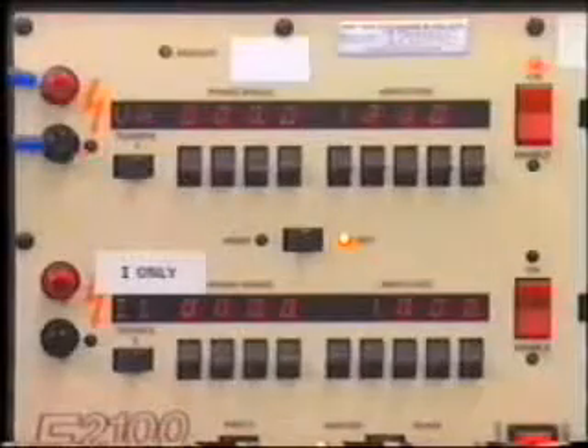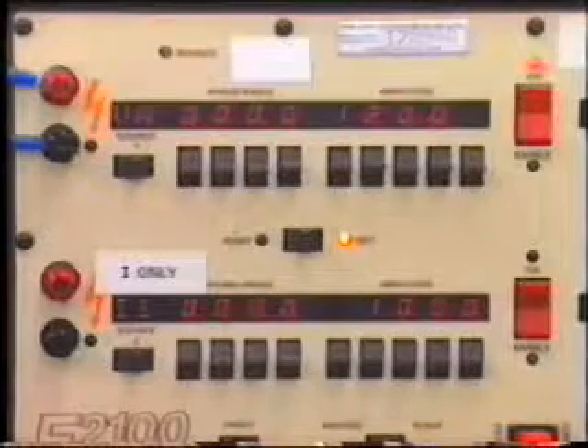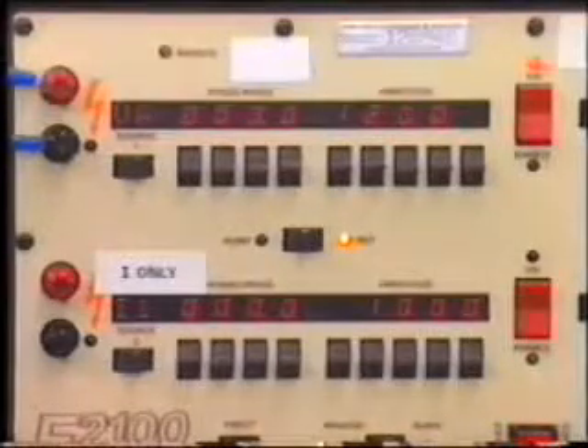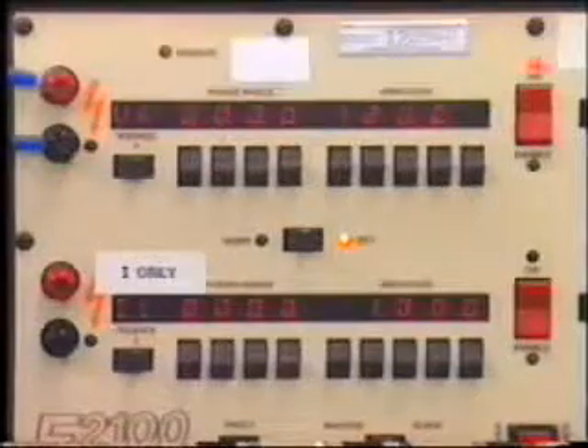Where computers are used, the test sets can play back actual faults which were recorded by digital transient recorders, including high-frequency transients. New DC-coupled slave sources can even reproduce DC offsets of voltage and current waveforms. Some digital distance relays have adaptive characteristics which change their reach and angle depending upon pre-fault load parameters. Now, these characteristics can be verified. Under computer control, all output voltages and currents can be changed simultaneously from pre-fault to fault conditions. This same dynamic test capability works well for testing the fault location accuracy of digital relays.